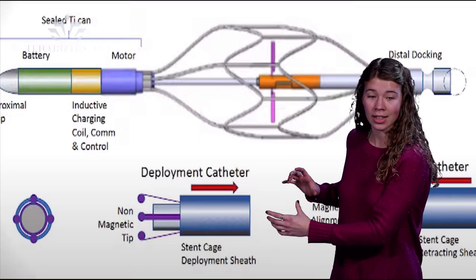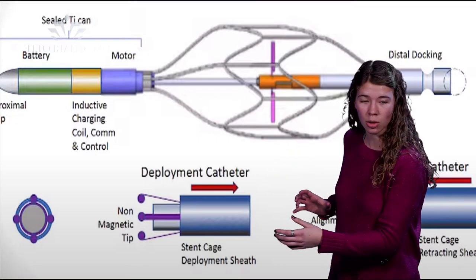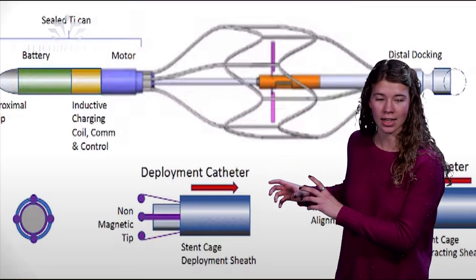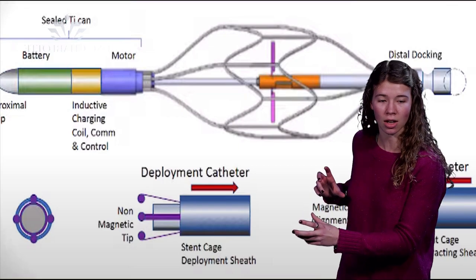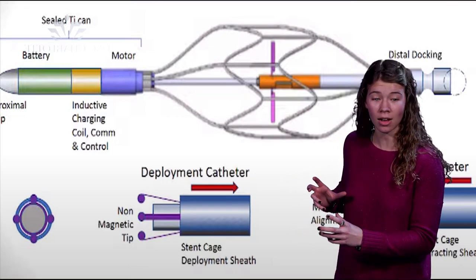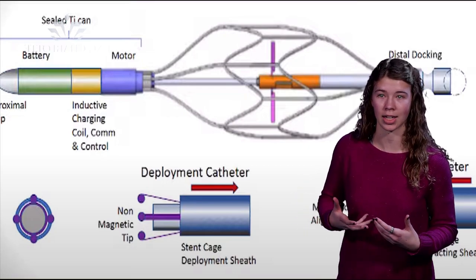This VAD is charged wirelessly to an external battery pack, but there's also a small backup battery inside the stent in case connection to the external battery pack is lost. However, this battery only lasts about 15 minutes and does not leave the patient with much time to get help if a connection is lost.